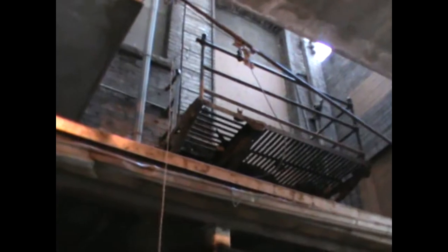Now, rivets or square head bolts. If it's rivets, it's 75 to 100. If it's square bolts, it's 50 to 75. But if you see any rivets, it means it's older than 75 years. How can you tell the backside? Look at the rounds. Those are called rivets. See next to it, square head bolts. Okay. So now look at all the gussets and the blowouts. Look at all the bulges everywhere, telling you what's happening behind those bulges.